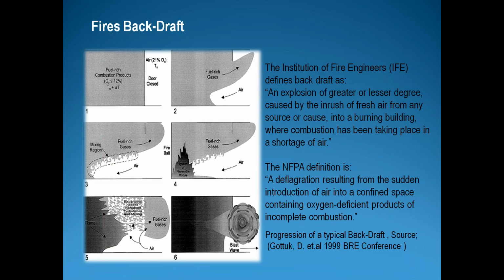Simply, you have an amount of oxygen inside the space. This oxygen will be reduced as the fire increases, because the fire takes the oxygen and gives us carbon dioxide. After a while, you will have a lack of oxygen, so the combustion of the fire will be incomplete. So beside the carbon dioxide, you will have carbon monoxide. The reaction of the carbon monoxide to become carbon dioxide is very strong and leads to something like a boiling of the fire or a bomb. So this is the background. If we add sufficient air to our system, we will protect ourselves from the backdraft or even from the flashover phenomenon.